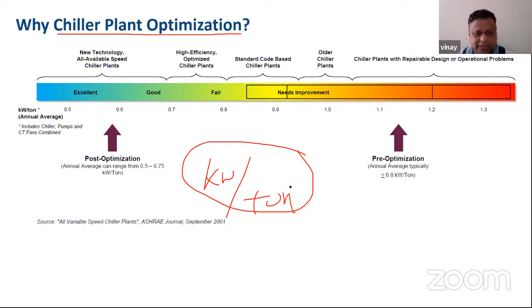0.5 kW per ton is a very common target number, and I'm encouraging those here who can work on the chill water plant. There are intelligent algorithms like MPC and machine learning where we can produce some kind of controls, so the kW per ton can get to around 0.5. If we are getting like 1.0 instead, then we need an improvement - we need to find out those buildings, mostly old chiller plants, and get it down to around 0.5.